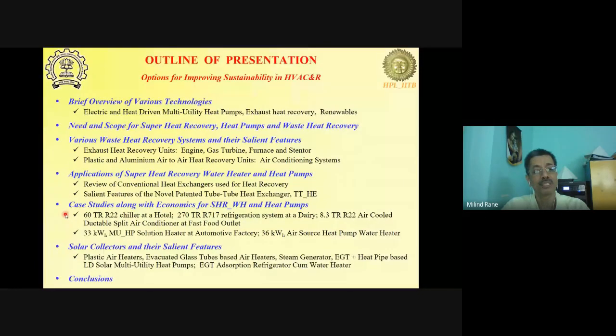After that, we'll briefly look at various case studies for superheat recovery and heat pump systems that we have developed and deployed on our own, through my own company, which we operated for about 3 years, and then licensed to various manufacturers, and then they have continued the deployment. So we'll look at the 60-ton R22 chiller in a hotel, which supplied hot water to the hotel for around 11 years without a single service call.